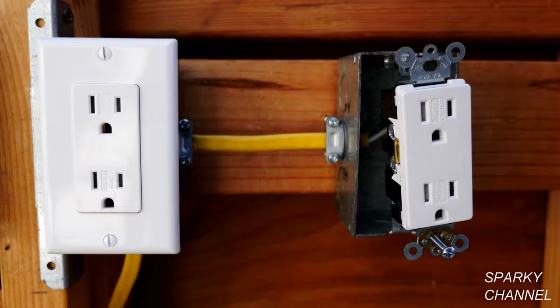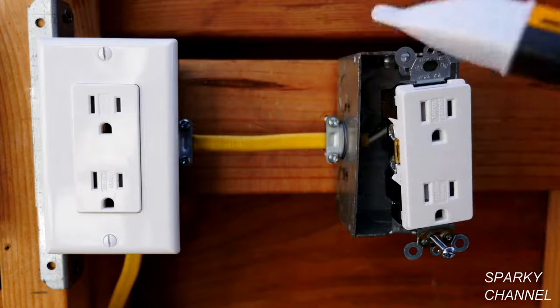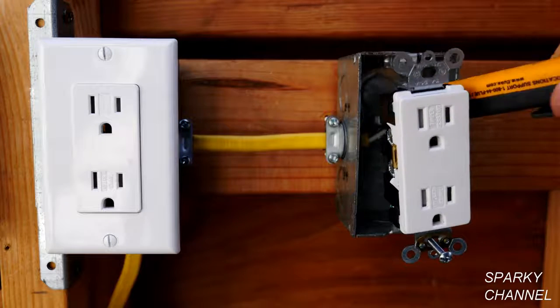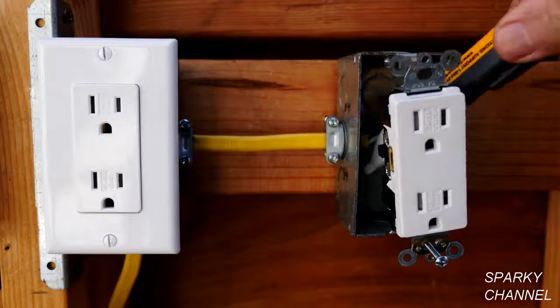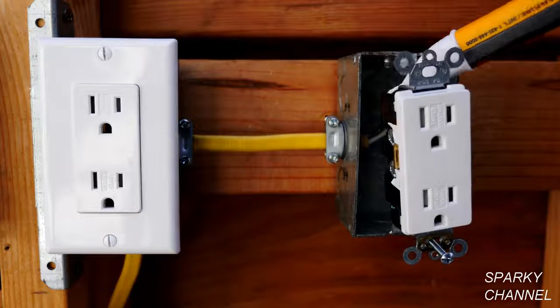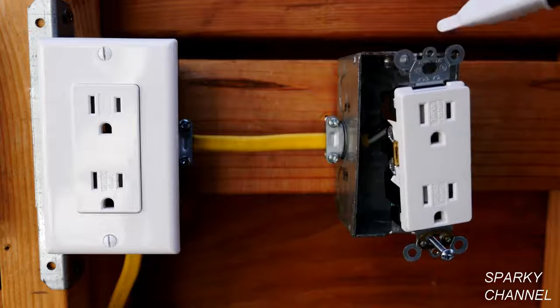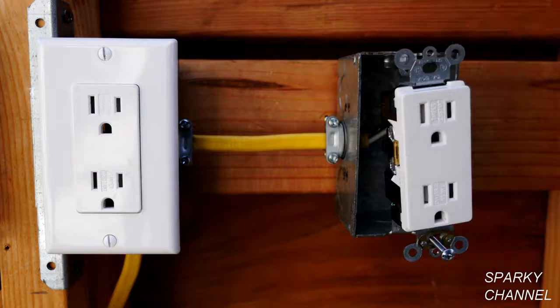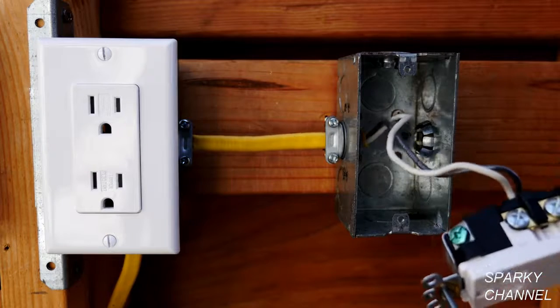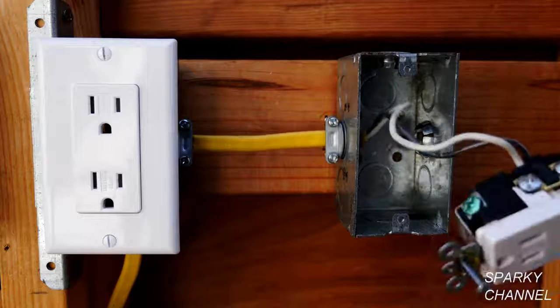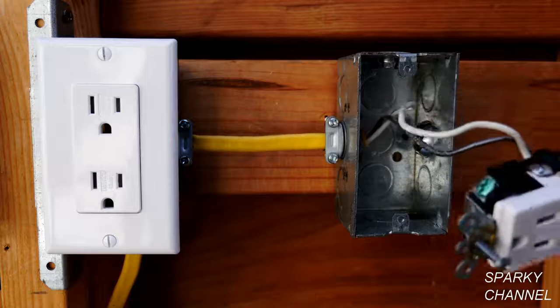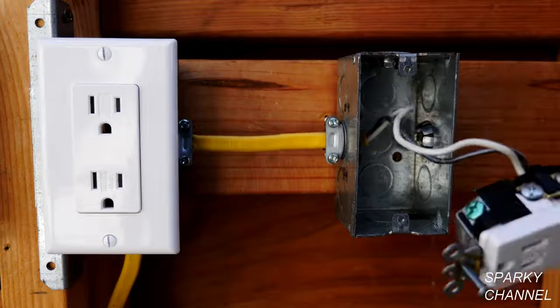I've loosened up the receptacle and the first thing I'm going to do is use my voltage detector and see if there isn't a hot wire back in the back of the box or something like that. And we see that all the electricity is indeed off. So we'll pull this out and we see that there's a neutral wire and a hot wire, but there's no ground wire. So that's our problem here. There is no ground wire.